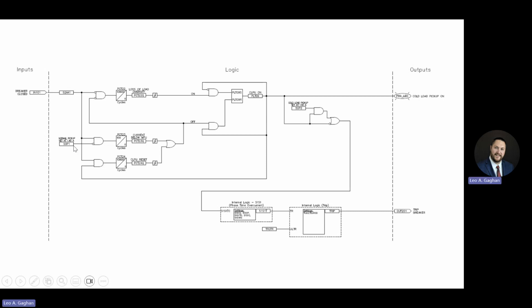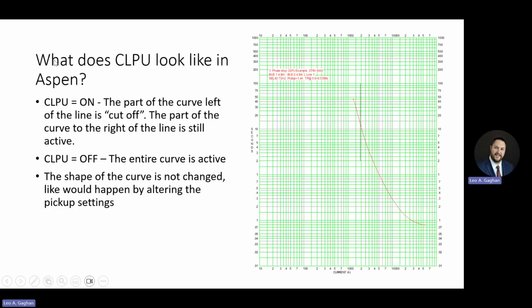What happens here is we have this overcurrent element set. If the pickup is above that normal pickup, it'll prevent this guy from timing, because it knows that we are above that normal threshold, and we're actually experiencing that cold load, the thing that we don't want to fault trip for. What will eventually happen is that current will come back down, and when that current comes back down, this pickup here will deassert, it'll go through that NOT gate, and this timer will start timing.